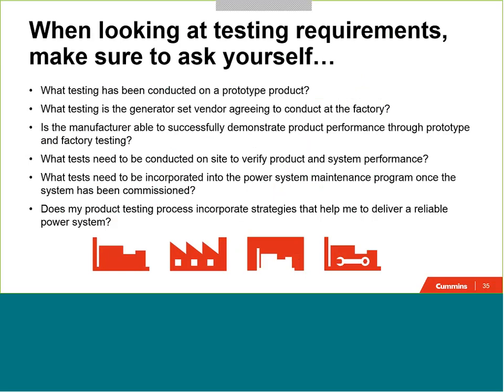Again, not all vendors are conducting prototype testing in the same way and at the same depth, and it's important to ensure for your power system that you're able to understand and decipher between the testing that has been conducted from different manufacturers. Try to look for more details, ask for certification of compliance, or ask for compliance with your testing requirements that are also conducted at the factory.